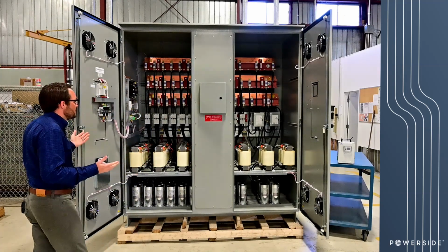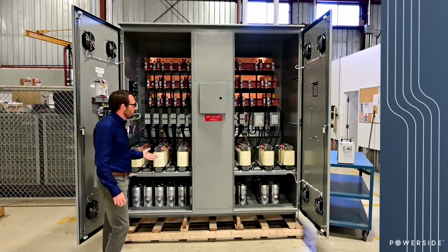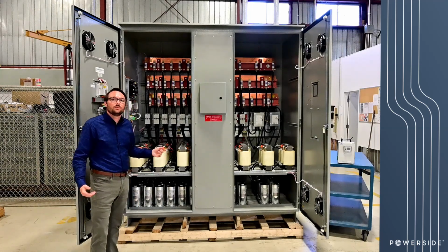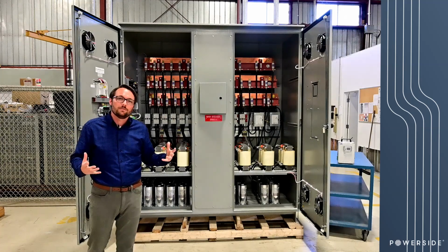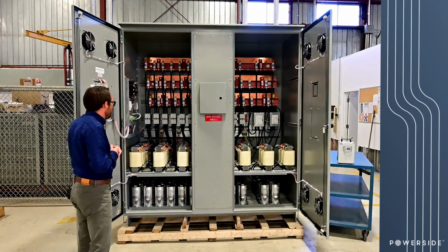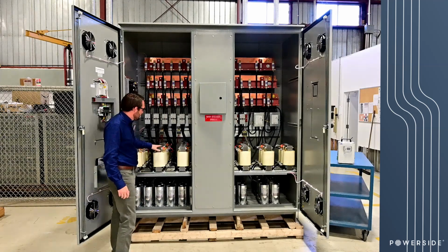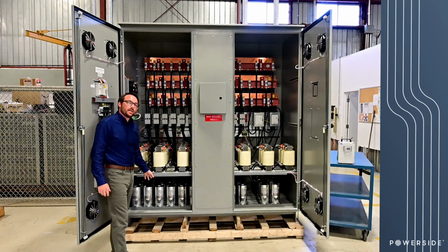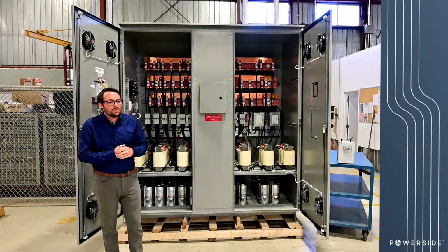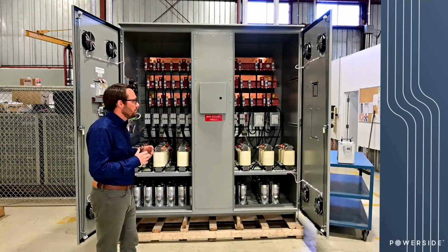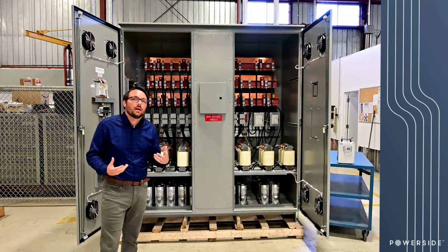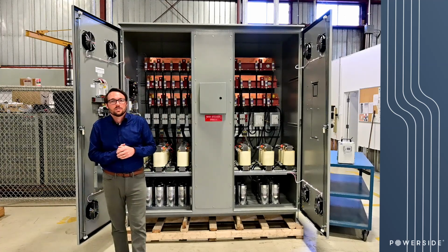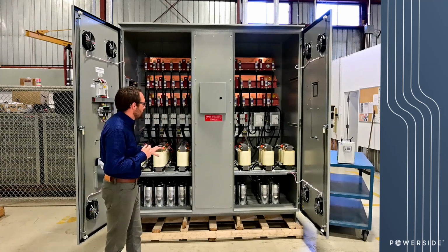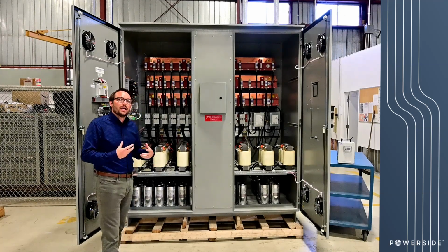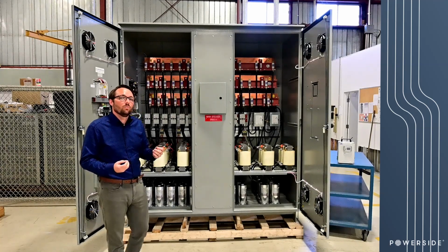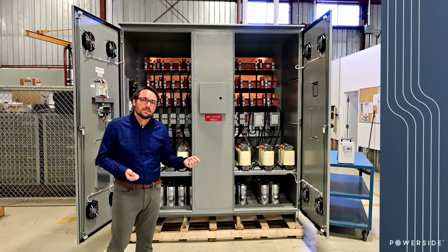And of course, you may notice here that this is not just a standard capacitor bank. This is technically what we call an LC filter or a shunt filter. And what that means is we have reactors which are in series with our capacitor cells. The reason we do that is because of the proliferation of nonlinear loads in the modern electrical power distribution network. What we're trying to do is prevent these capacitors from amplifying or creating a resonance with the harmonics that exist in the system.